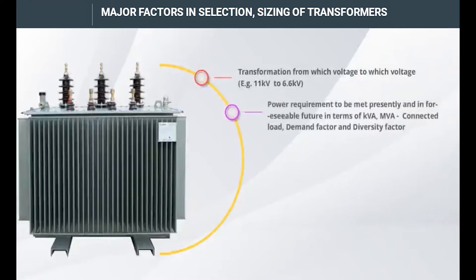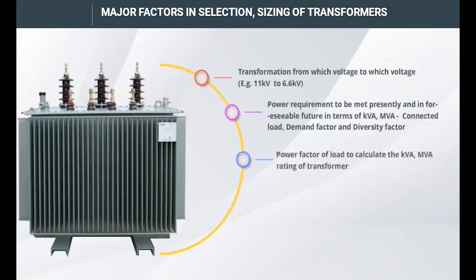Power requirement to be met presently and in the foreseeable future, in terms of kVA, MVA, connected load, demand factor, and diversity factor. The power factor of the load is also needed to calculate the kVA and MVA rating of the transformer.